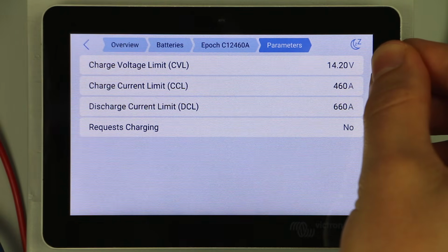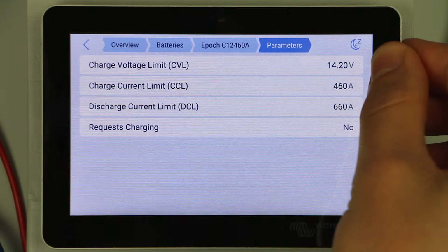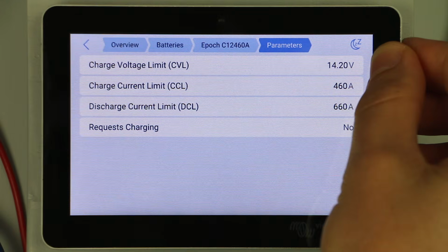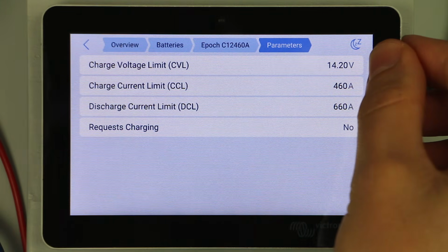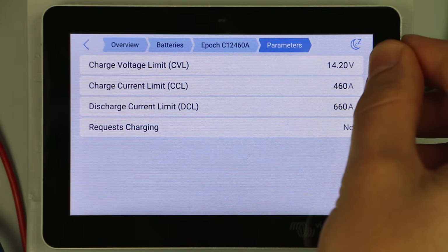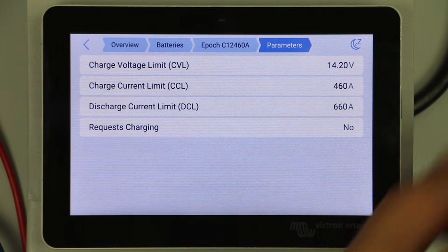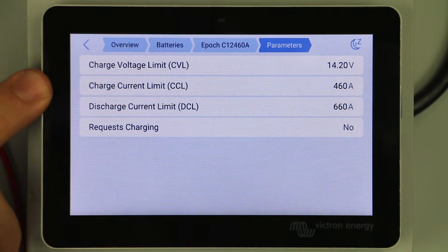That is an absorption voltage for these particular batteries. Once they're done with their absorption cycle, that is going to drop to 13.5 volts, and the batteries are just going to float at that lower voltage. Basically they are going to be able to tell the chargers, do not go any higher than 13.5 volts until this number changes back to 14.2 and the batteries are ready for another absorption cycle.